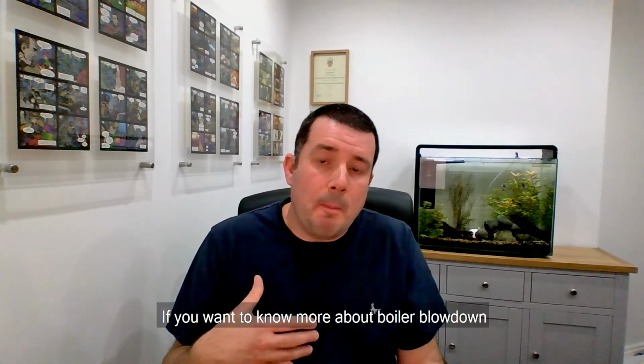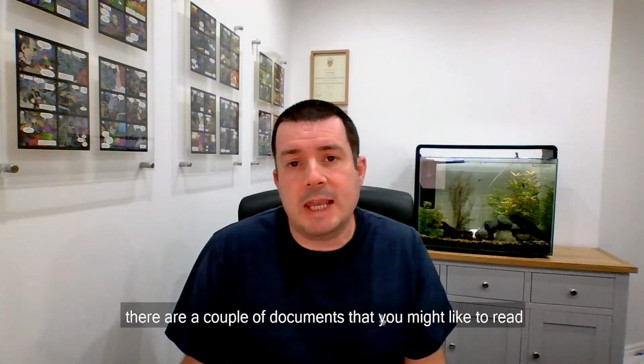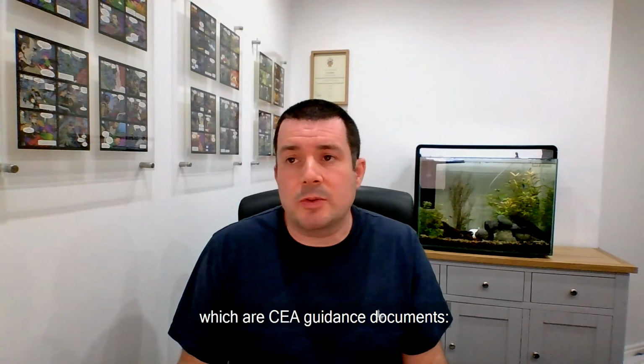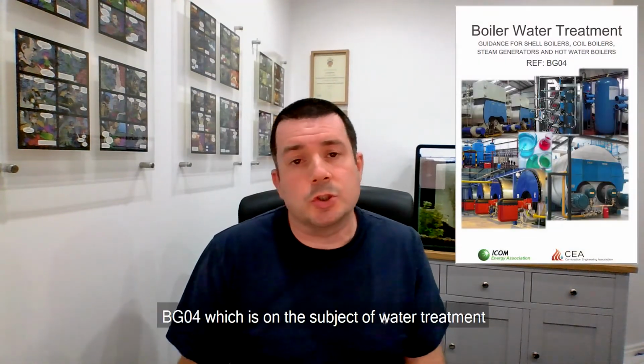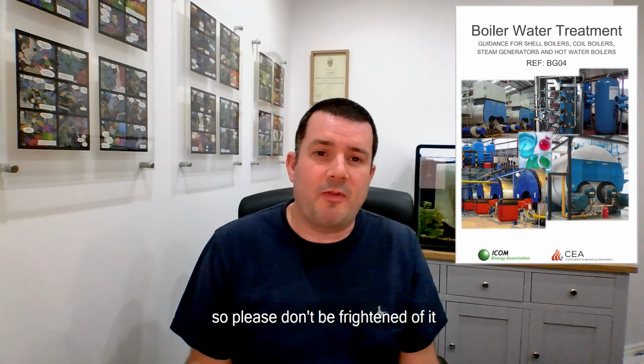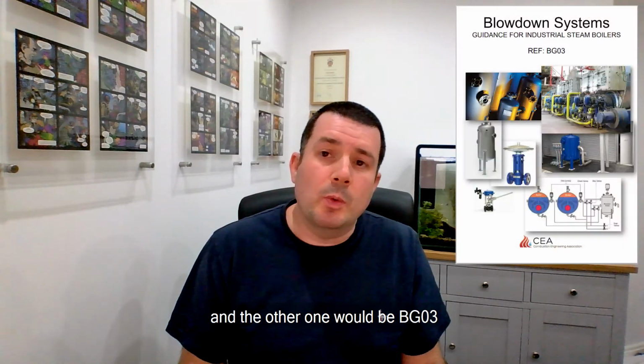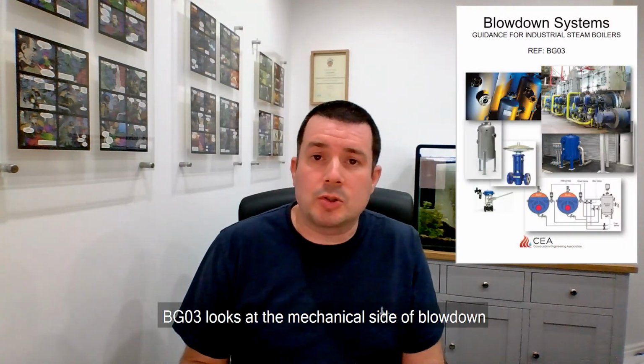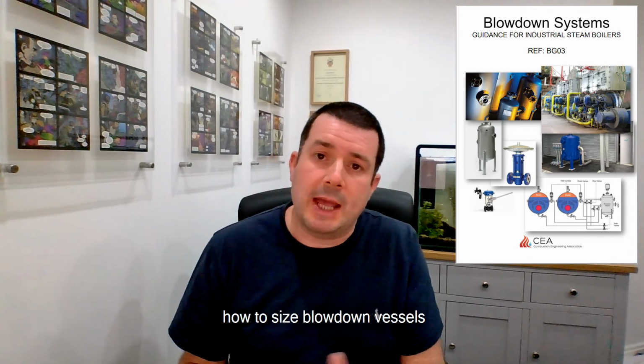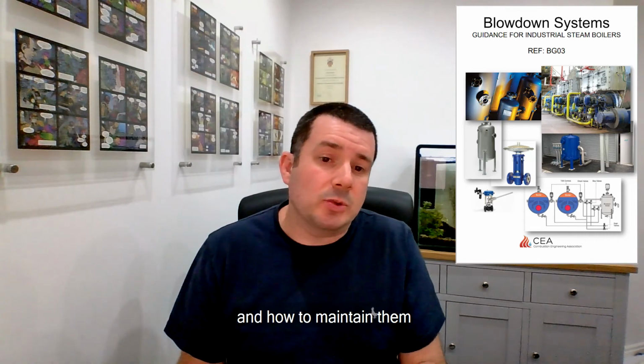If you want to know more about boiler blowdown, there's a couple of documents that you might like to read, which are CEA guidance documents. So you've got BG04, which is on the subject of water treatment. It's not a chemistry book, so please don't be frightened of it. And it's a definite read for all engineers. And the other one will be BG03. BG03 looks at the mechanical side of blowdown. So it looks at pipe construction, how to size blowdown vessels, how to install them, and how to maintain them.